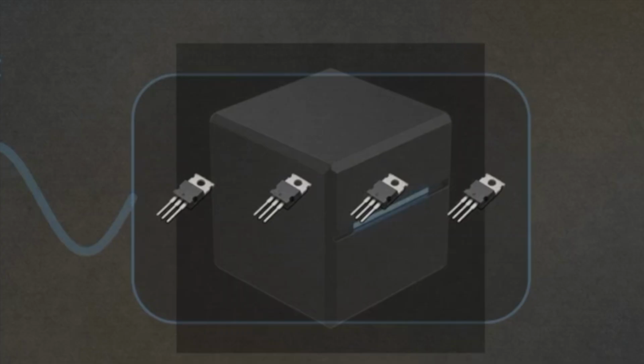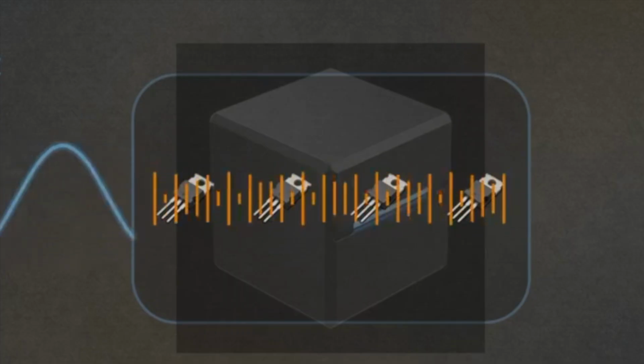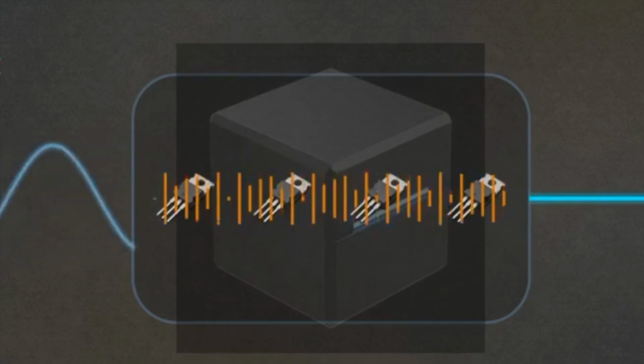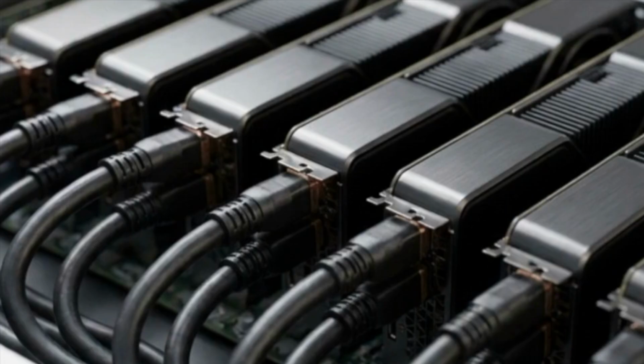The critical semiconductor enabling this high-frequency switching is high-voltage silicon carbide. Watch the circuit path: the solid-state transformer converts medium-voltage AC grid power directly to DC power, without the need for a massive steel core. The 800-volt DC output matches the exact internal power architecture required by next-generation AI GPU racks.